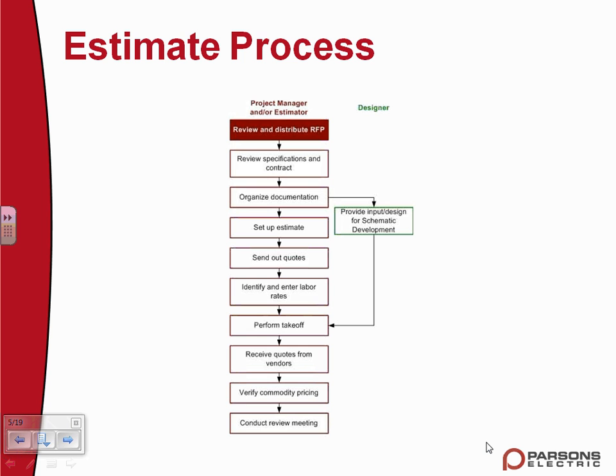If we're doing one of these checks, like the number of light fixtures per square foot in a hospital, we usually run around 40 square feet, maybe 35. If one of the sheets comes up at 60, we know which one it is. We can go to that sheet, look at the counts, do a recount, and see if we've got an error, or if there's some anomaly, like a storage space or something to be finished later.